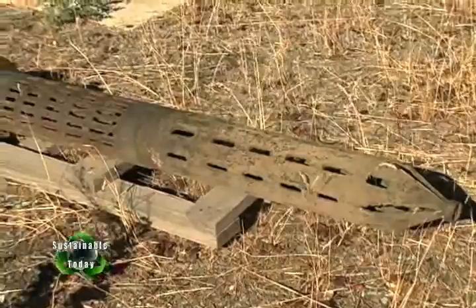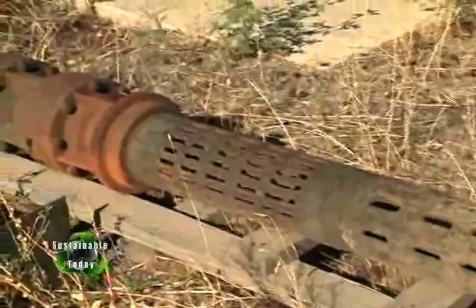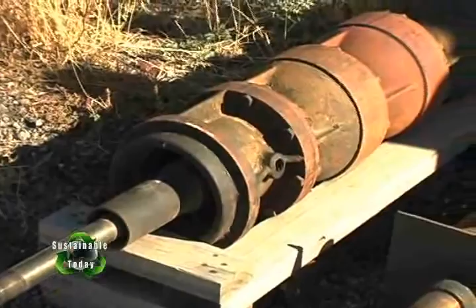These are the actual pumps that are at the bottom of the well column. The perforations you see are where the water is inlet, and above that is the bowl assembly. The shaft is turned by that motor we looked at earlier, and that drives the impellers which are in this bowl assembly. That actually elevates the water, brings the water from the aquifer up to the surface level.